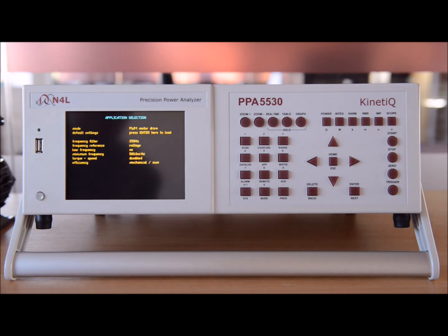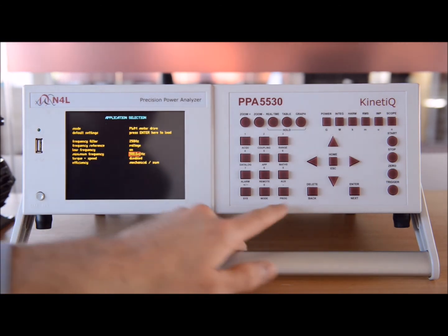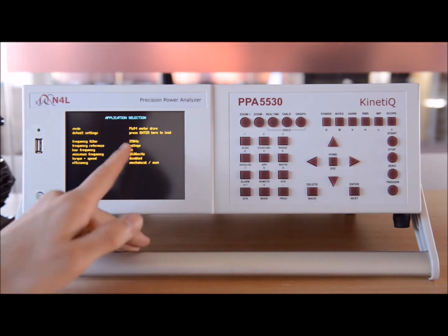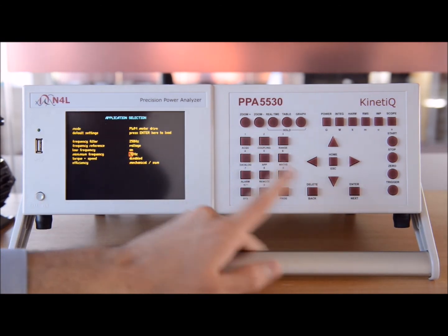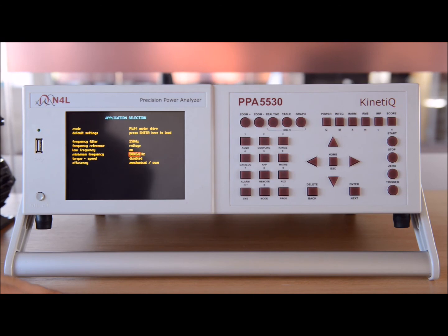So if you are never going to go below 5 Hz, set the minimum frequency to 5 Hz. Anything below that can be considered DC. It's just so that the instrument doesn't sit there waiting forever, because the lowest possible frequency that we can detect is 10 millihertz, which is a long period there, long fundamental period. And of course you need one cycle before you get an update on screen. So if you're at 1 Hz, the maximum update rate for the analyzer is going to be 1 second.